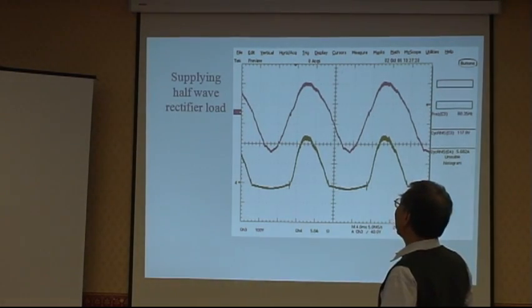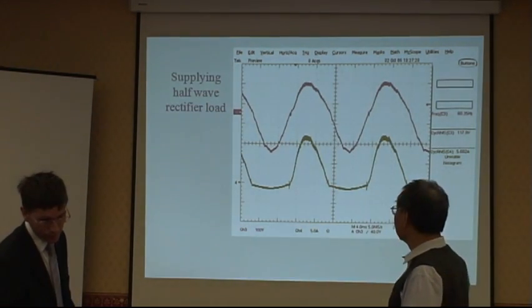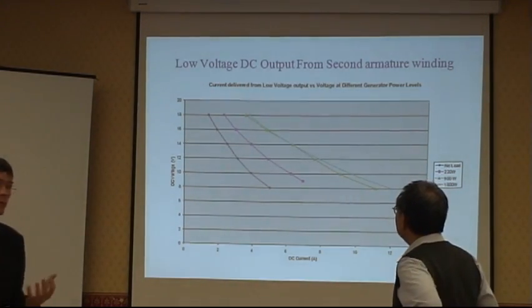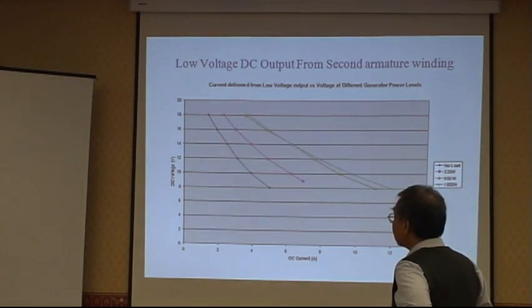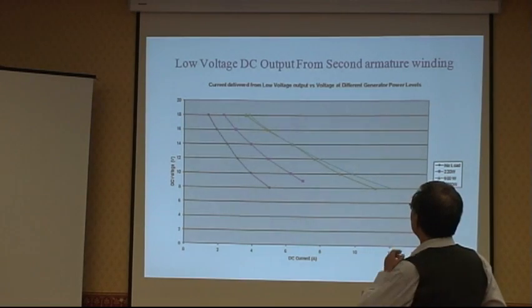But the output inverter, a little bit distorted, but maintains very good output voltage. 虽然吃半波，但是电压波形看起来也没有变太多，只有下半波差一点点，看起来跟正弦波也蛮接近的。We also from the generator, we have a low voltage armature winding to do battery charging.